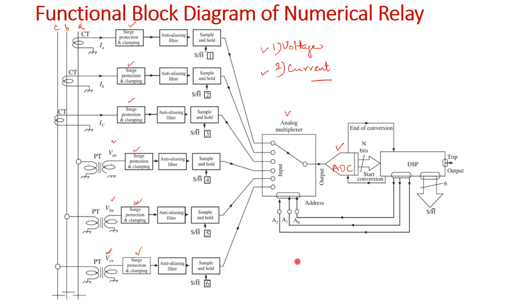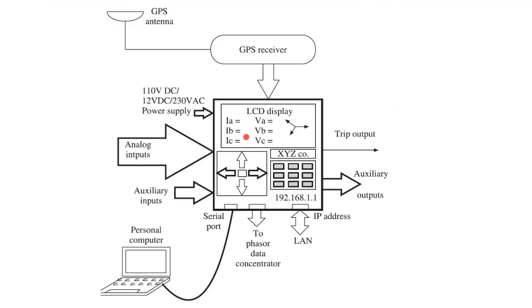Okay. Nowadays, relays have been modified a lot, particularly the numerical relays, because the numerical relay is now imbibed with many functions, and presently it has also been integrated with PMUs. PMUs are nothing but the phasor measurement unit, right? PMUs play a very important role in system parameter monitoring, right? So we can see in this figure a numerical relay which is measuring the parameters in a synchronized manner, right? GPS plays a very important role, that is, the global positioning system antennas.